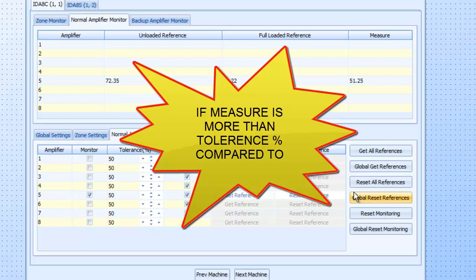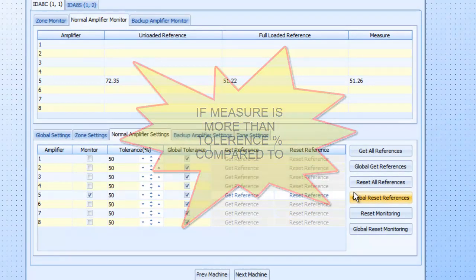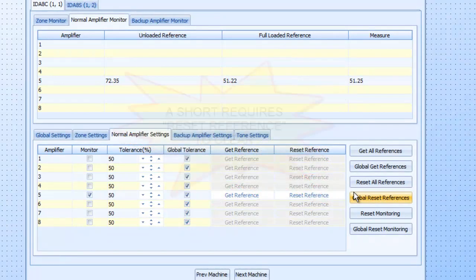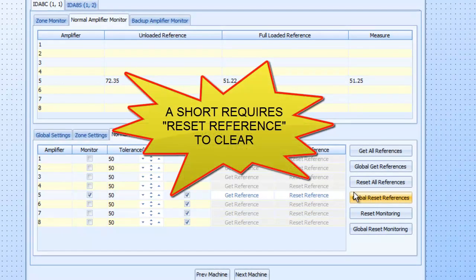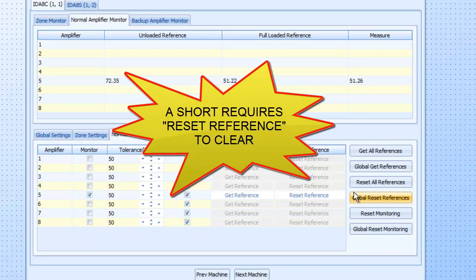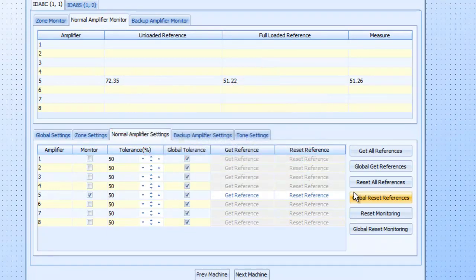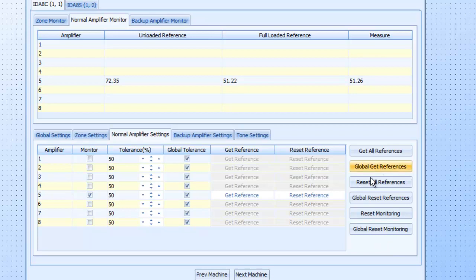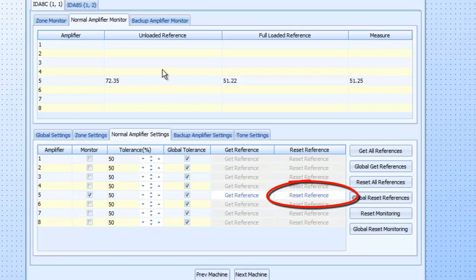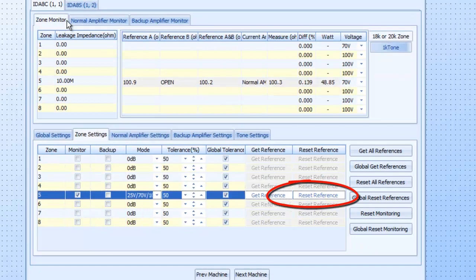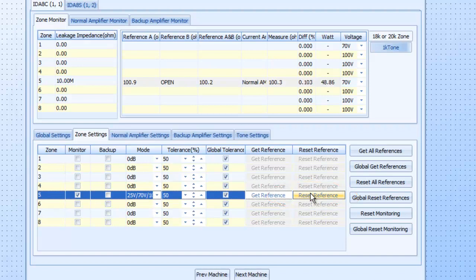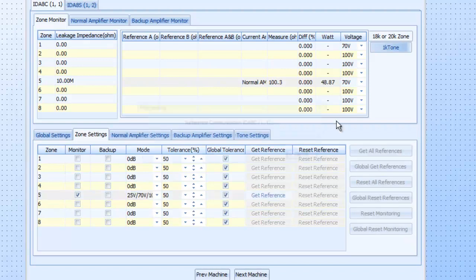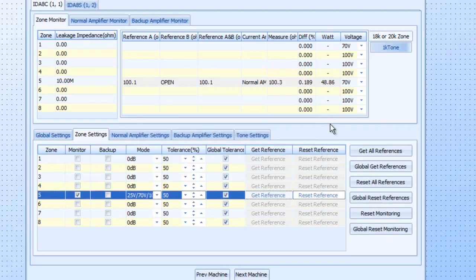The other thing is if you have a short on a speaker line, the system will protect itself and it will disconnect that output automatically if there's a short or a ground on the positive leg that produces an overload. And when that happens, you'll get your error. Then at that point, once you fix the system, that is where you have a reset reference comes in, the reset reference will allow you to reset that system. And once you've repaired your short or ground on the positive leg, you can click reset, which I'll do here. There you go. And then you can say re-get. You heard the beep.